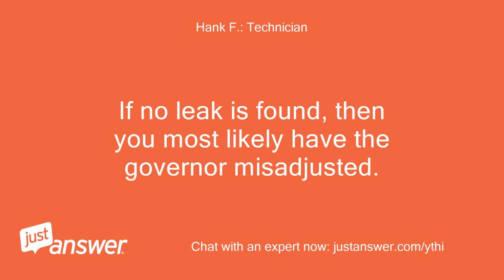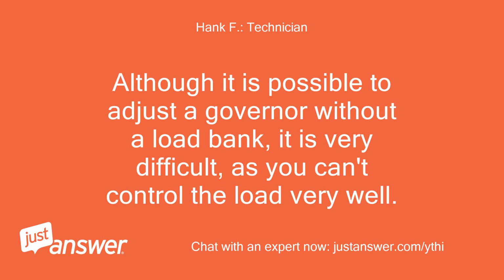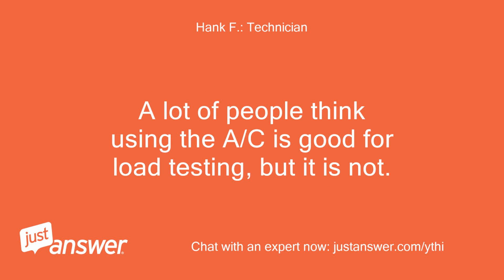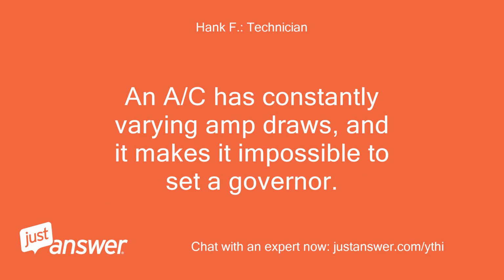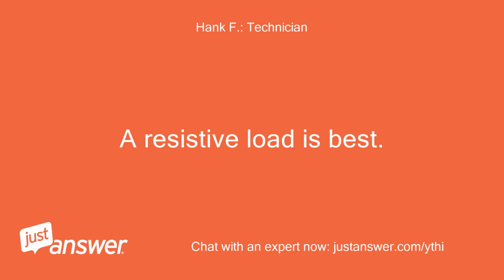If no leak is found, then you most likely have the governor misadjusted. Although it is possible to adjust a governor without a load bank, it is very difficult, as you can't control the load very well. A lot of people think using the AC is good for load testing, but it is not. An AC is constantly varying amp draws, and it makes it impossible to set a governor. A resistive load is best.